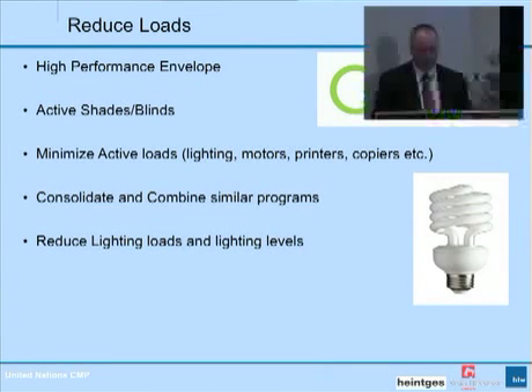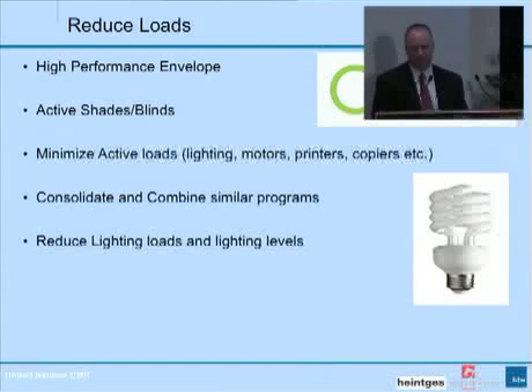Reducing the loads. What are our MEP systems responding to? One of the first steps is to reduce the amount of cooling and heating required, and what are we reacting to? We're reacting to the envelope. So we worked closely with Bob Heintges and his team and the project team on both the program and the building systems, and also the level of insulation in the wall. Active shades and blinds. We visited other buildings that had incorporated this kind of technology, including the New York Times building and Bank of America, to see what had worked and what hadn't worked for them, and incorporated the best of those technologies in our campus.